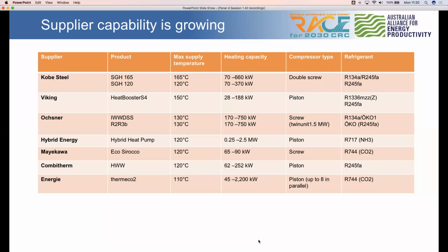In terms of another enabler for heat pump technology being adopted, we're certainly seeing the supplier capability growing. Here's a list of heat pump suppliers, mainly coming from Europe, that are doing high temperature. I could have listed a lot more suppliers for lower temperature heat pumps, but these are the ones doing the high temperatures. And you see the very high temperatures, say 130 and above, is mainly done by refrigerants which will likely be phased out. But certainly when it comes to ammonia and CO2, the natural refrigerants, up to 120 degrees, no problems at all.